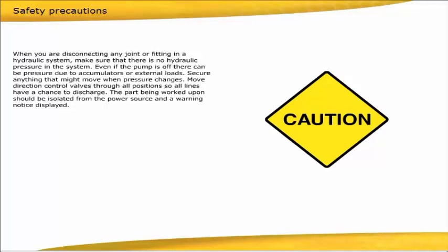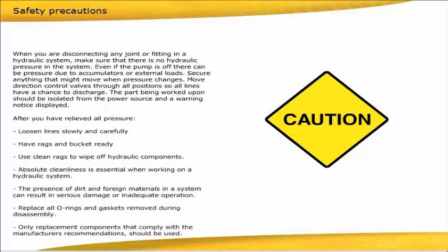Secure anything that might move when pressure changes. Move direction control valves through all positions so all lines have a chance to discharge. The part being worked upon should be isolated from the power source and a warning notice displayed. After you have relieved all pressure, loosen lines slowly and carefully.